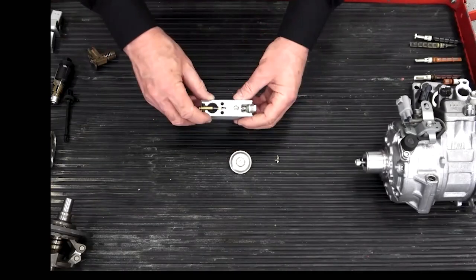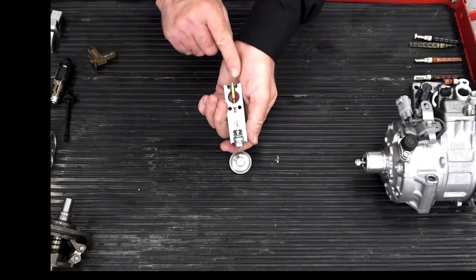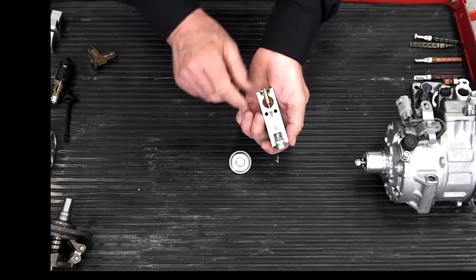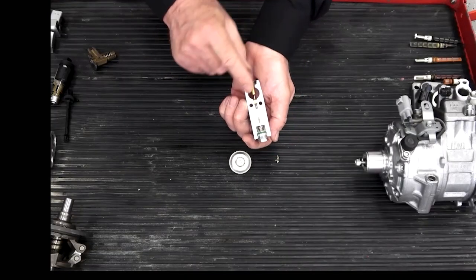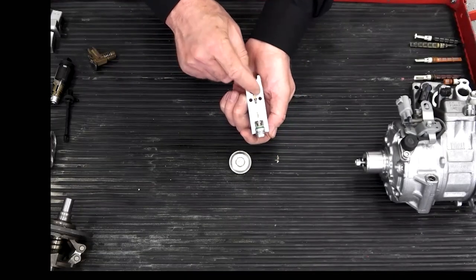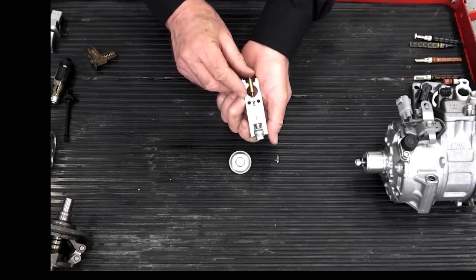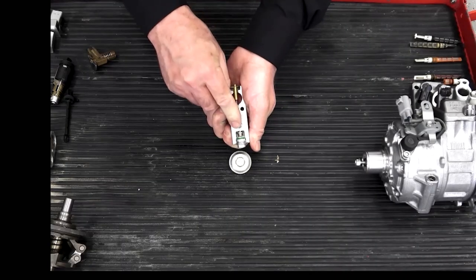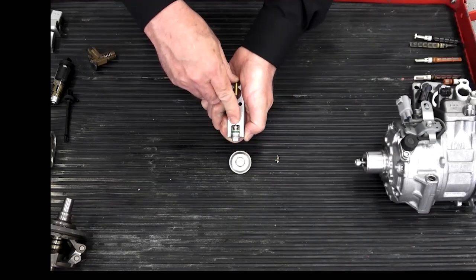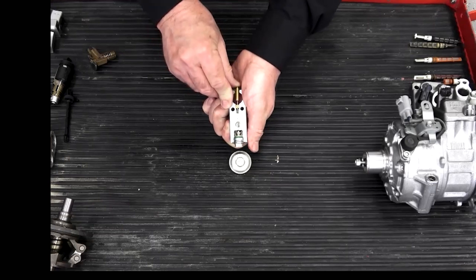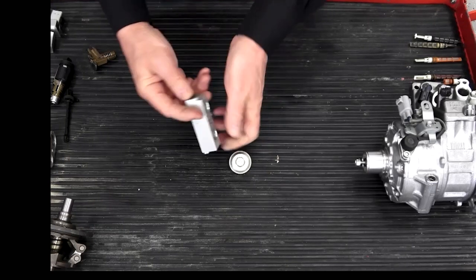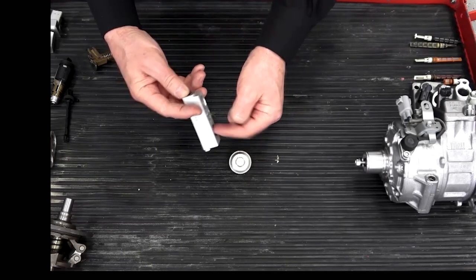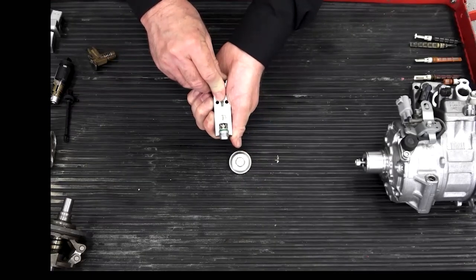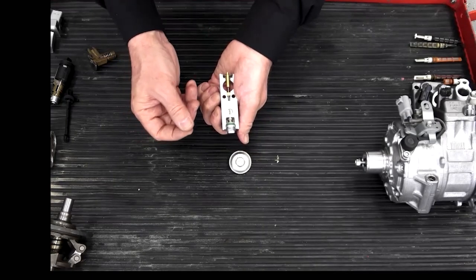And so the way this works is this. You see there's a rod here that runs all the way from the power element down through the valve, from the outlet, the suction side, all the way to the inlet where the liquid comes in. If I push on this rod, it's pushing down on a ball valve. You see there's a ball bearing right there? So it's pushing that ball valve. If I have liquid refrigerant coming in here and I push that ball valve off its seat, I'm going to get more liquid refrigerant into the evaporator.